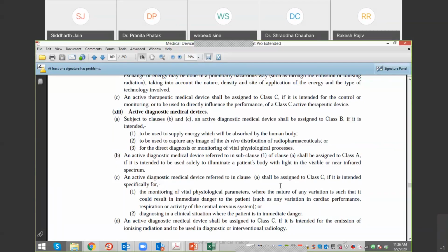You can just see point number A of active diagnostic medical devices: subject to clauses B and C, an active diagnostic medical device shall be assigned to class B for the direct diagnosis or monitoring of vital physiological parameters. So you just have to see whether the software has a direct impact or direct danger to the patient. If it has a direct danger to the patient with respect to cardiac performance or the central nervous system, then it will be a class C device. If it is not, then it will be a class B device.